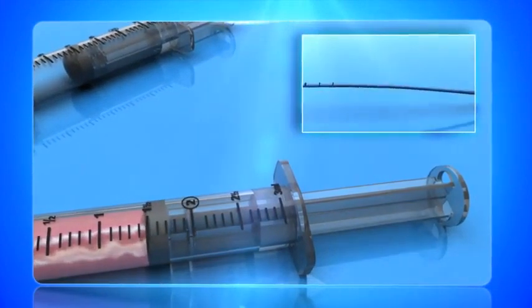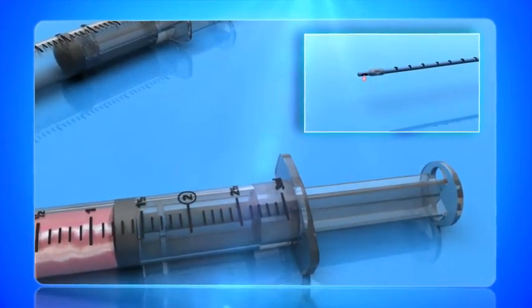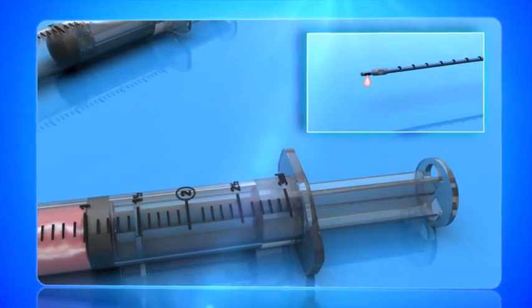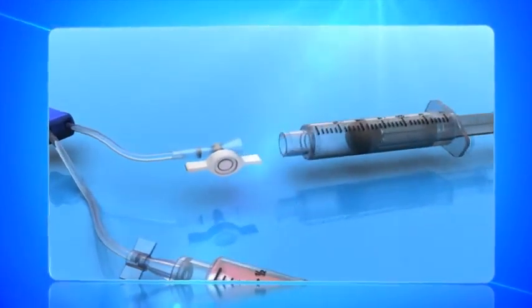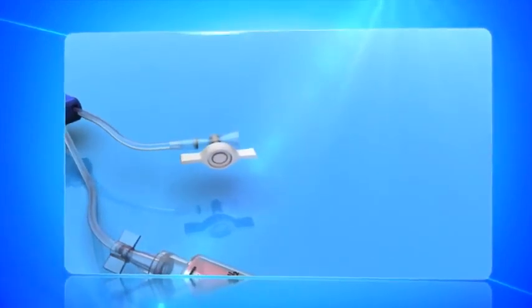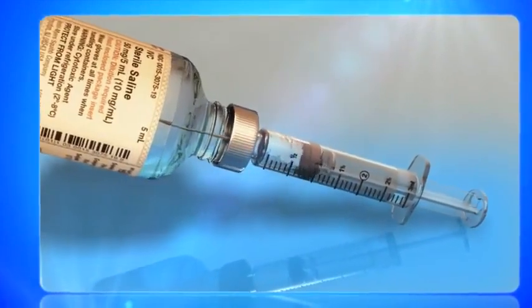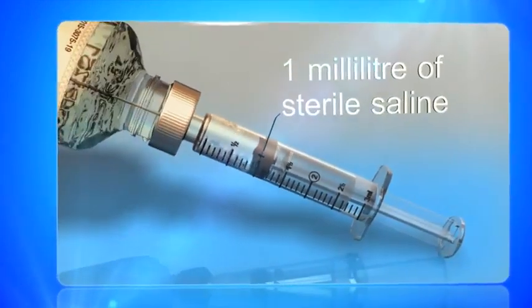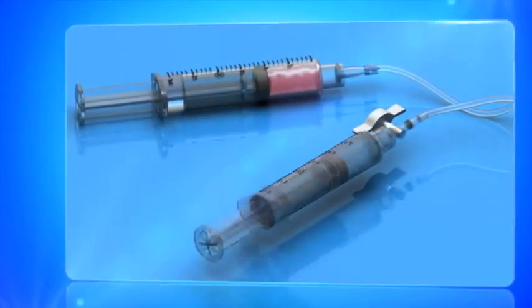Prime the catheter by advancing the insemination syringe to the 1 milliliter setting and do not disconnect. Disconnect the balloon inflation syringe from the balloon inflation line of the catheter. Fill the syringe with no more than 1 milliliter of sterile saline solution. Reconnect the balloon inflation syringe with the stopcock open.